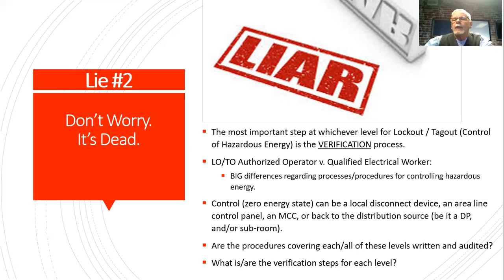If the authorized employee goes through their steps, hits the button, and the machine starts, they have not verified the lockout. They don't have verification, they're going to have to call for help. That's another time when your qualified electrical worker is going to use testing equipment to achieve a zero energy state. You can have local disconnects, you can have line control panels, you can have an MCC, you have your distribution, be it a distribution panel or a lighting panel. It goes back to the subroom. This is important. Knowing how far back something goes is important, so that if you have to go to the next step, the next level, you can do so. We'll get to that when we talk about marking and labeling.